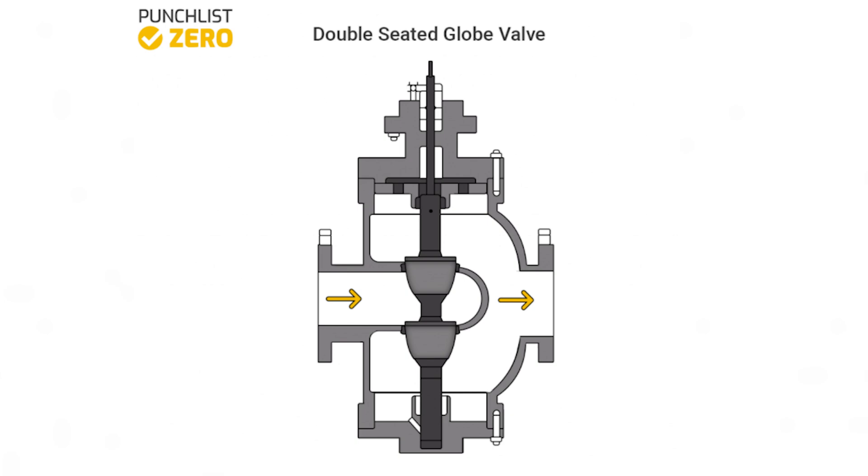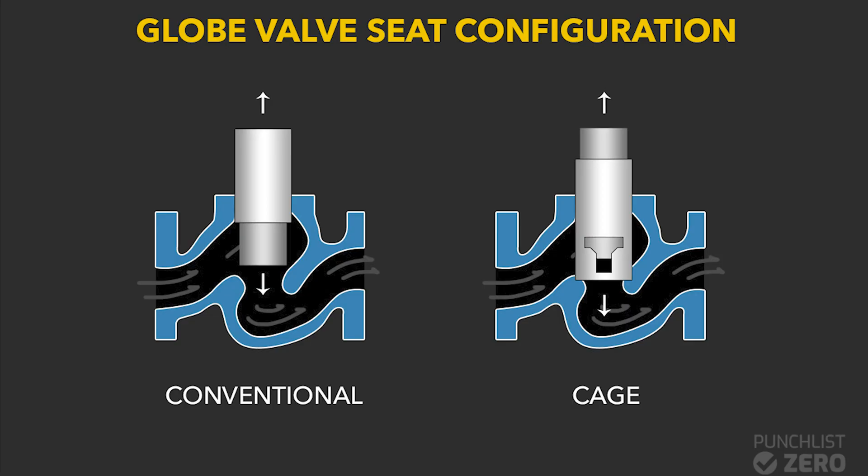In a conventional globe design, the process media directly contacts the disc. In a cage guided design, the cage isolates the plug from pressure and deflection. The cage guided design is not appropriate for viscous media, as the cage can become plugged.